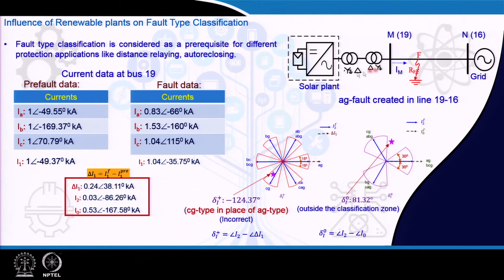You can see the current nature here is contributed by the solar plant. The current which flows through the relay is contributed by the solar plant. It is a phase A to ground fault, but the nature of the fault current is that the phase A current has gone down, and it tries to balance the corresponding current even though a phase A to ground fault happens to be there.